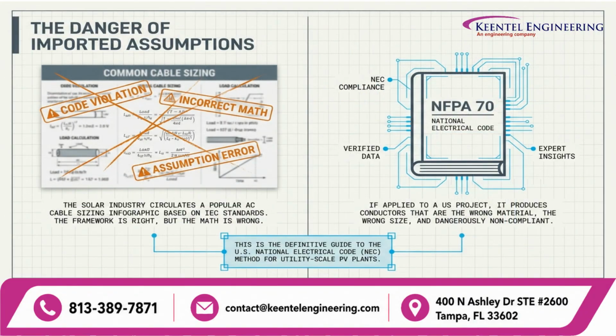Across our industry, a popular cable sizing infographic based on IEC standards frequently circulates. While the general engineering concepts seem familiar, applying those assumptions to a US project leads to severe code violations, incorrect math, and undersized conductors. When you take European or IEC rules and drop them into an NFPA 70 framework, you end up with non-compliant installations that risk safety and fail inspection. This presentation provides the definitive, verified US NEC method designed specifically for utility-scale solar.